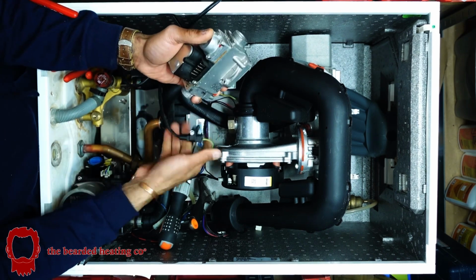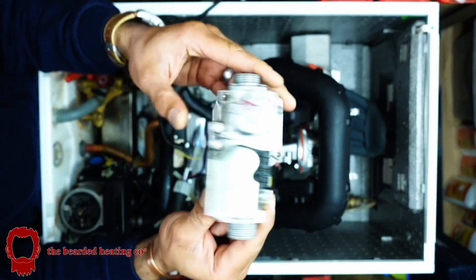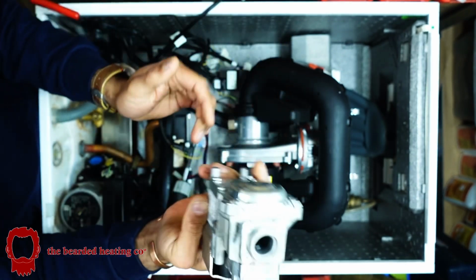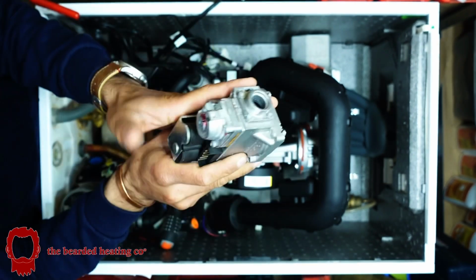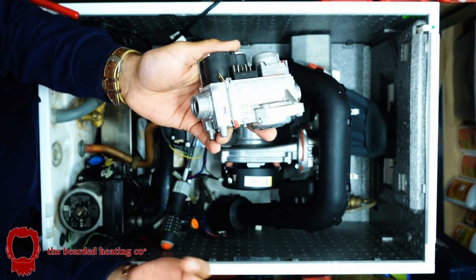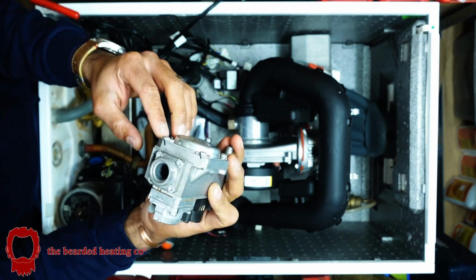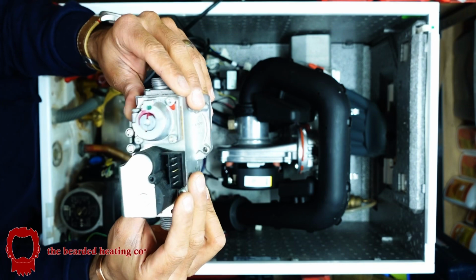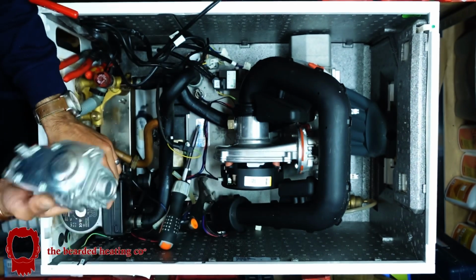But yeah, gas valve comes out. There's your gas valve, so gas valve's out. Another easy component to replace should you be getting ignition lockouts and other various gas failures as part of a boiler breakdown.